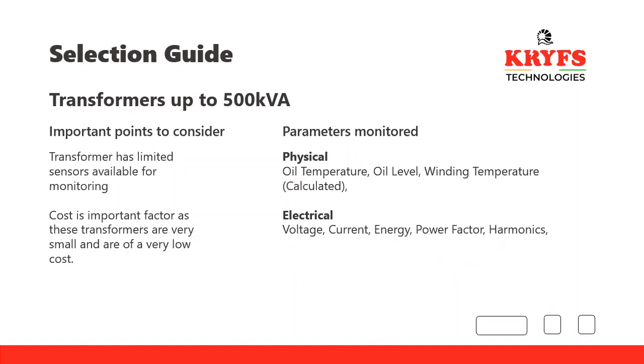Cost is a very important factor as the transformers are very small and are of very low cost. So here what we offer is that we offer basic parameters like oil temperature, oil level and winding temperature can be shown as calculated value. If the energy meter installed, we can have the voltage, current, energy and power factor, harmonics, etc. Okay.